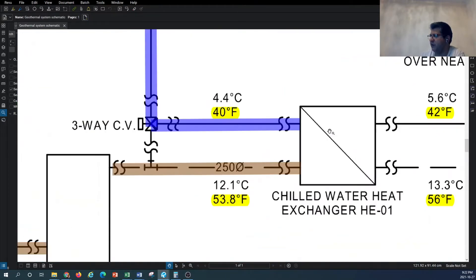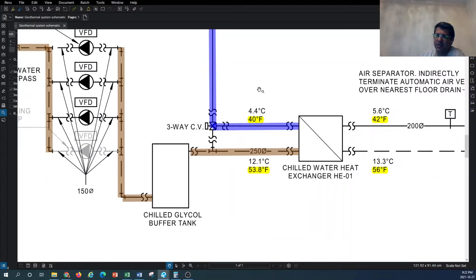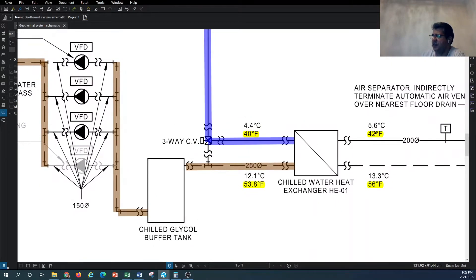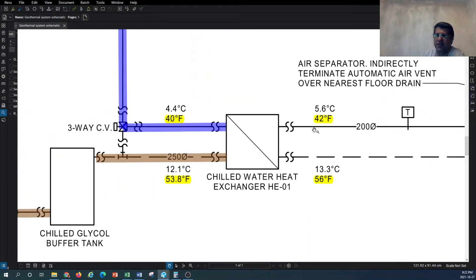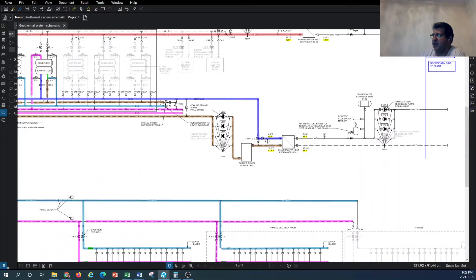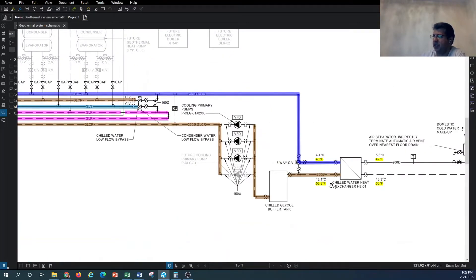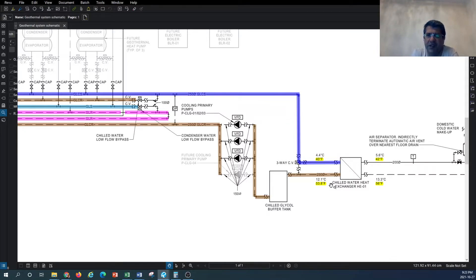On the right-hand side we have a heat exchanger where the chilled glycol arrives at 40°F and transfers the chilled water temperature into the secondary side of the chilled water line. The chilled water is picked up at 42°F and then distributed to the building cooling coils. When the chilled glycol enters the heat exchanger it loses temperature, and we aim to remain within approximately a 14°F delta T.